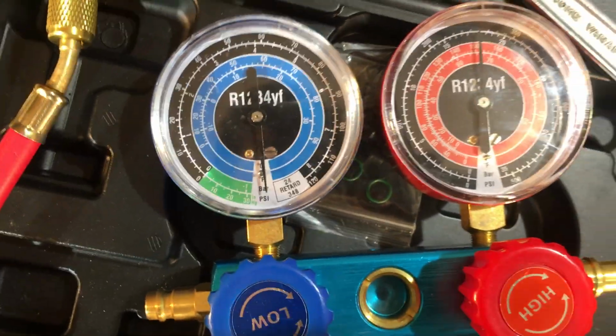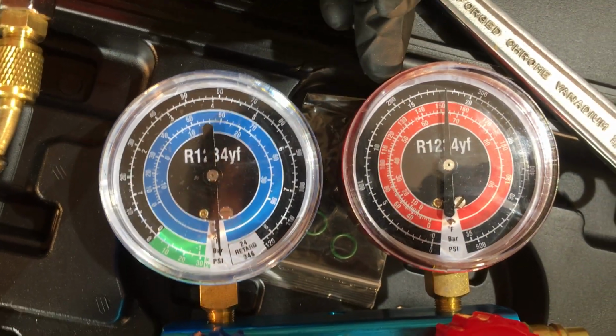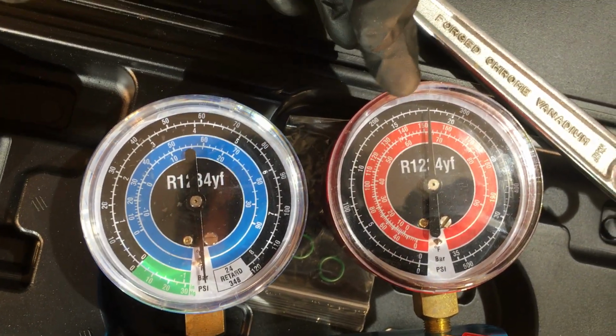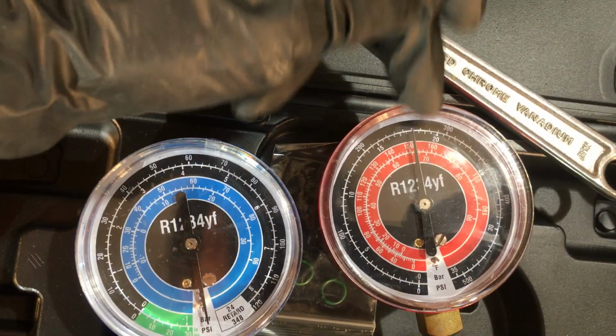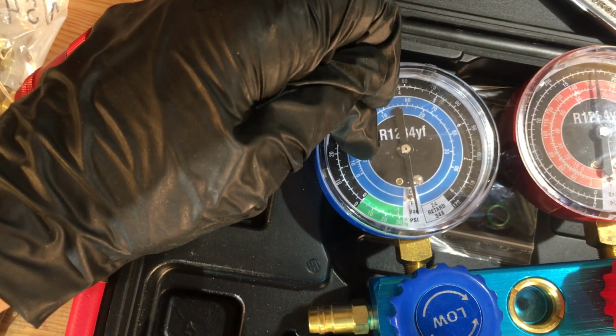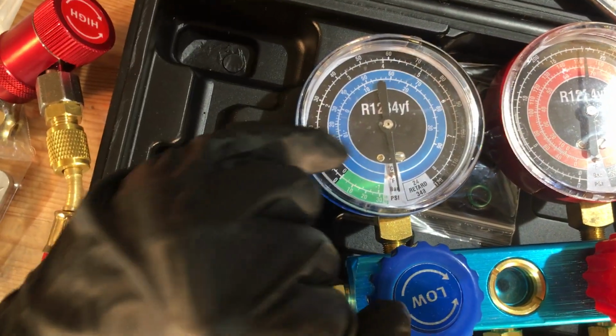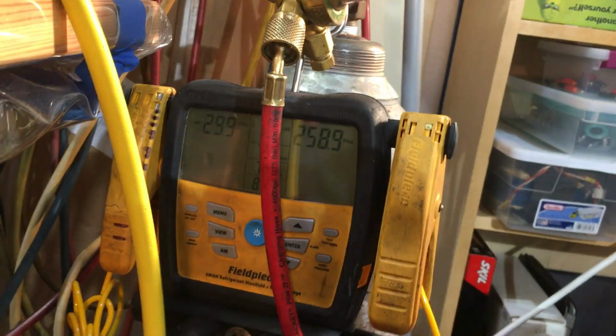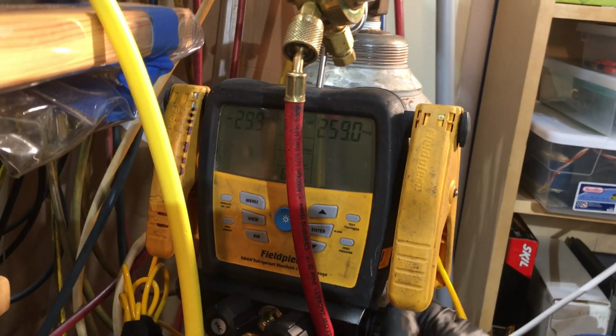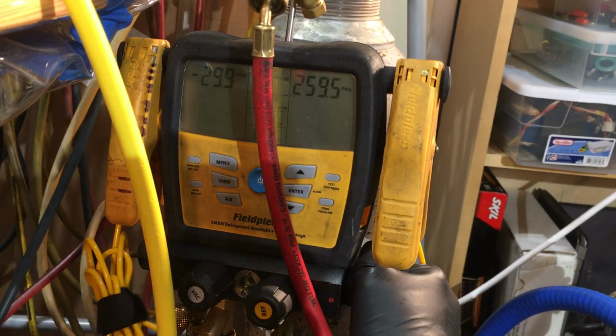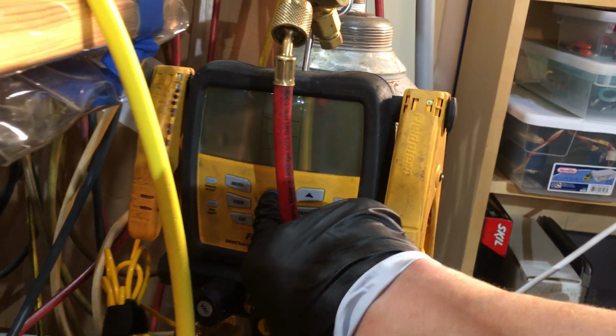255, 256 PSI. We come back to our gauge set. And we are at 210, 20, 30, 40, 50, almost 60. So on our high side it says almost 260. We definitely pegged it over here, which these gauges don't go up as far on the low side, which is bad for the gauge. I'll have to recalibrate it. 259, 258. So now I'll shut off the pressure, bleed the pressure to the gauges. Turn it back on. Just trying to get the light back up.